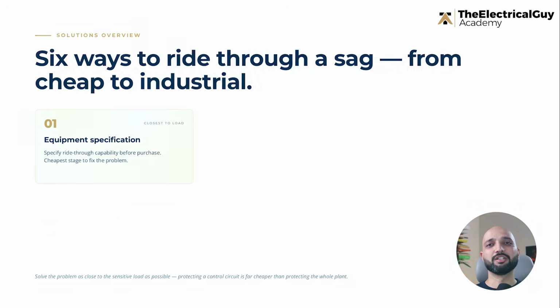The first solution is, of course, better equipment specification. When buying critical equipment, check its voltage sag ride-through capability. Ask the manufacturer how much voltage dip the equipment can tolerate and for how long. For critical industrial equipment, it is better to specify that the equipment should ride through common voltage sag conditions. Some industries follow standards and guidelines that define ride-through expectations for sensitive equipment. This is the cheapest stage to solve the issue because you are preventing the problem before installation.